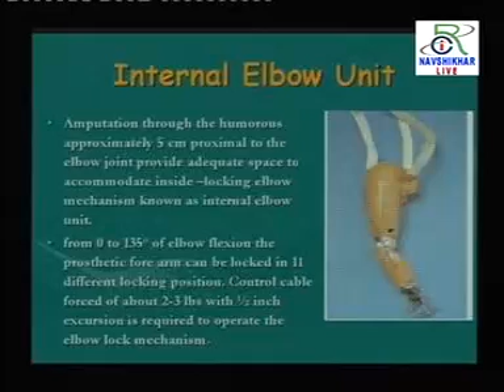An internal elbow unit: amputation through the humerus approximately 5 cm proximal to the elbow joint provides adequate space to accommodate the inside locking elbow mechanism, known as the internal elbow unit. From 0 to 135 degrees of elbow flexion, the prosthetic forearm can be locked in 11 different locking positions. A control cable force of about 2 to 3 pounds with half-inch excursion is required to operate the elbow lock mechanism. The internal elbow lock mechanism is used.